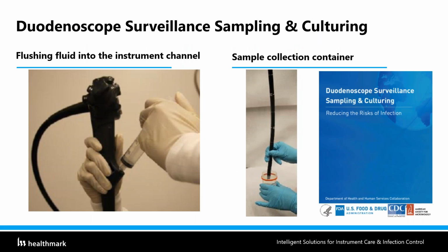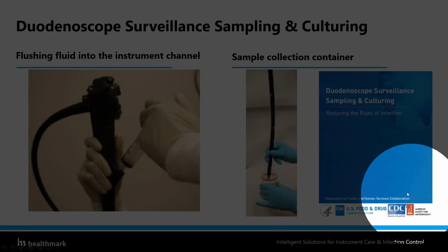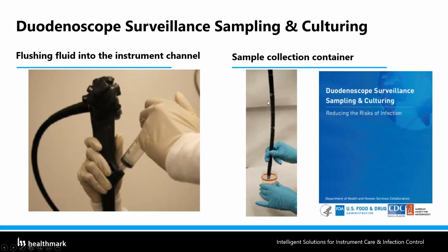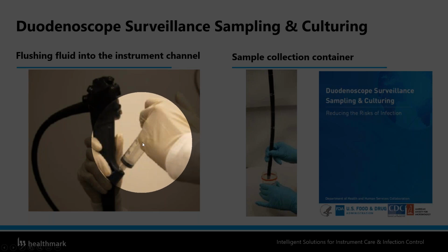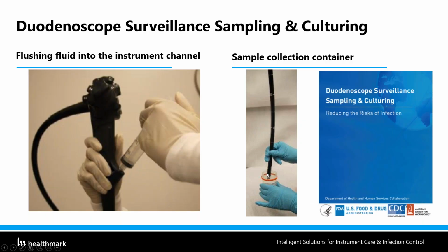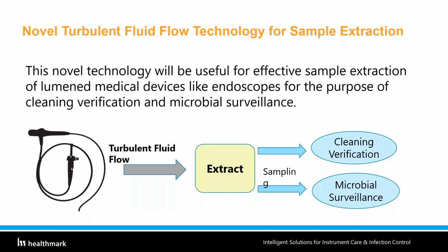Since we had these issues, the FDA and CDC came up with this 55-page guidance, which is available for download for free. Looking at that, for microbial surveillance you need to do sampling. In this case, you see that this person put in 20 cc of sterile water, followed by 60 cc of air, and then somebody else collects that sample and sends it to a lab for microbial testing. What we realized was that it was really difficult, you needed two people, and we found out some of our samples were contaminated with dry skin or the environment.